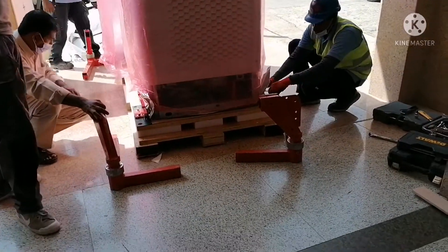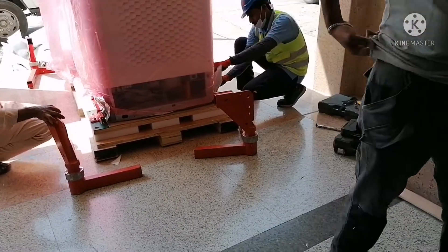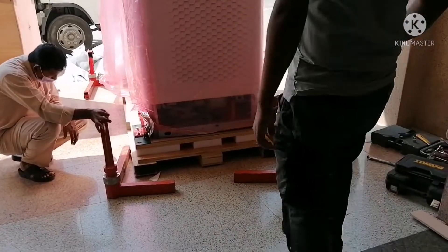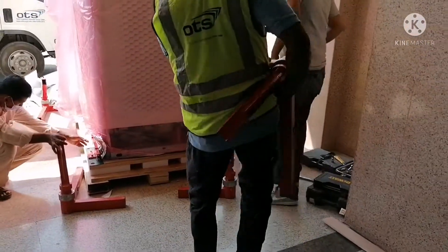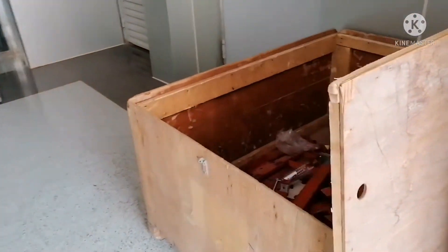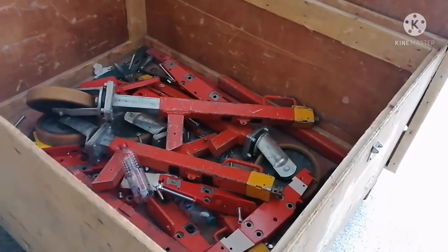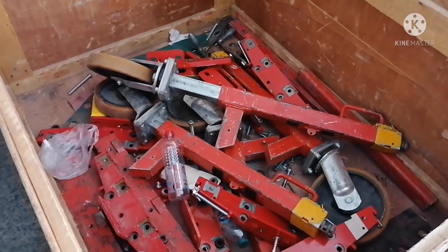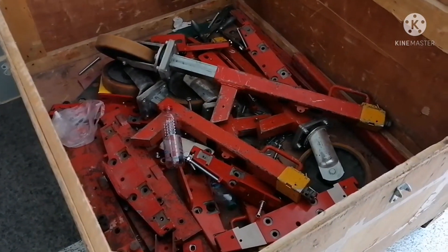The machine weighs 2 metric tons, or 2,000 kg. These are the transport wheels — the trolley that will be used to carry the machine and the gantry into the CT scan room.